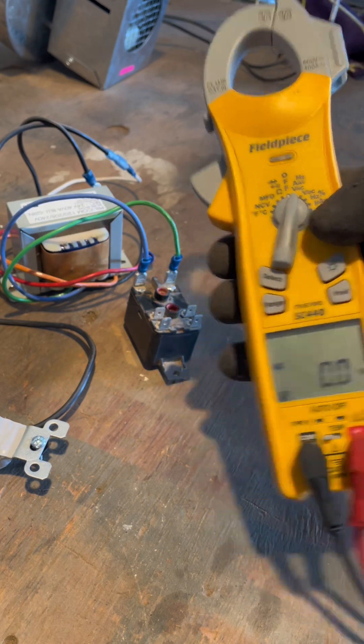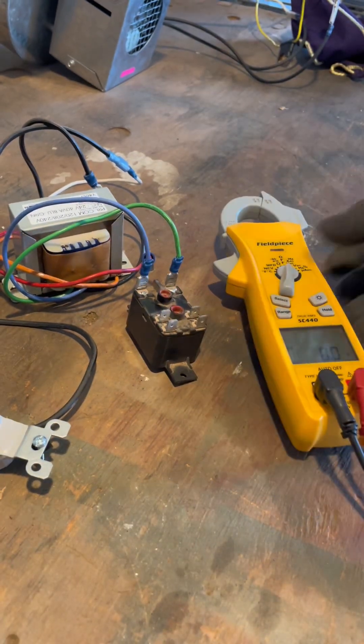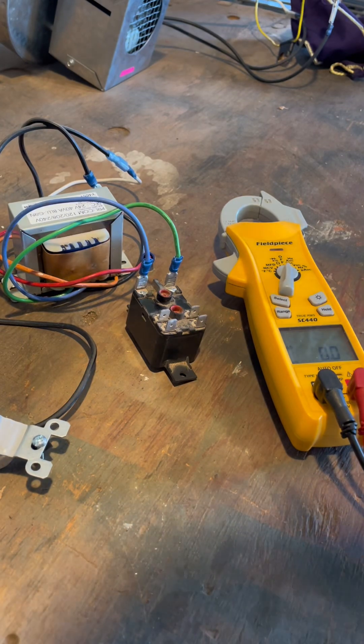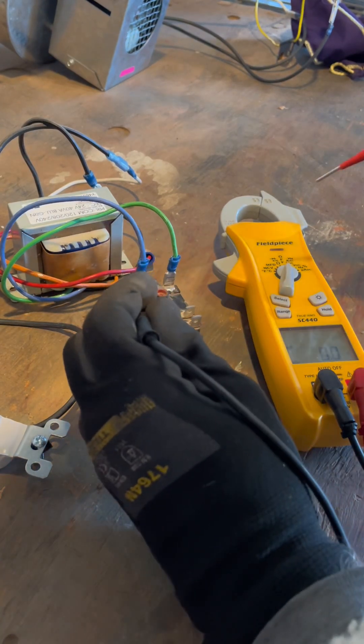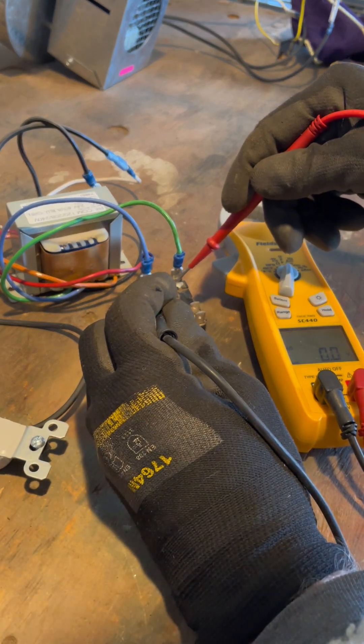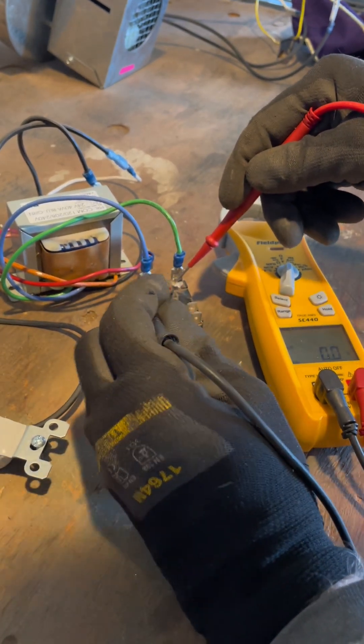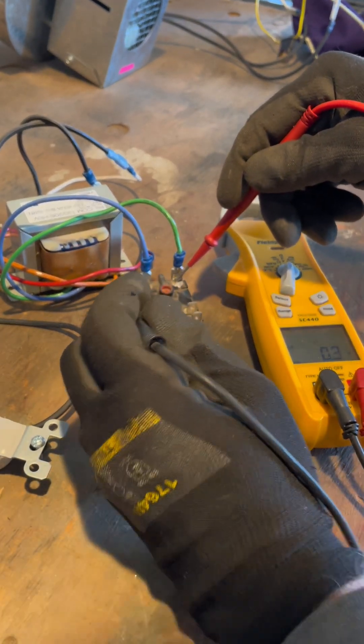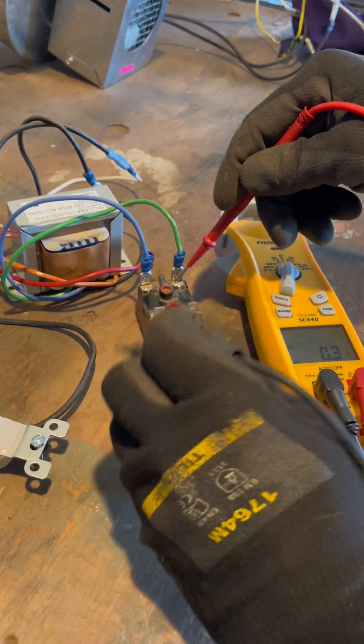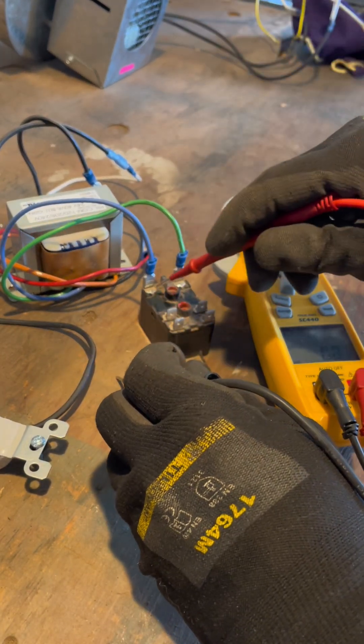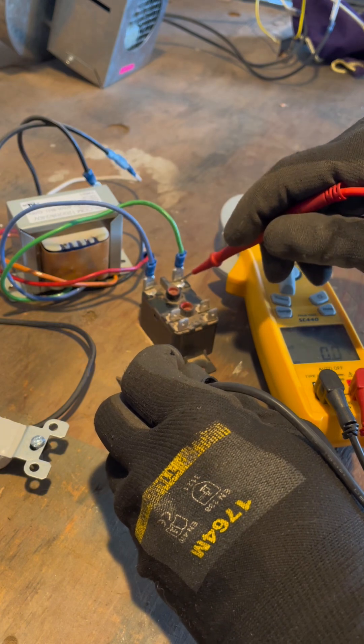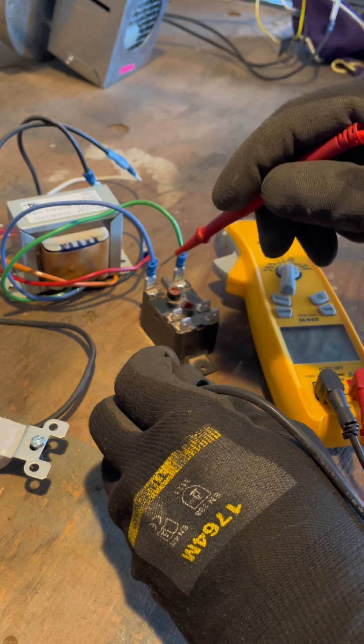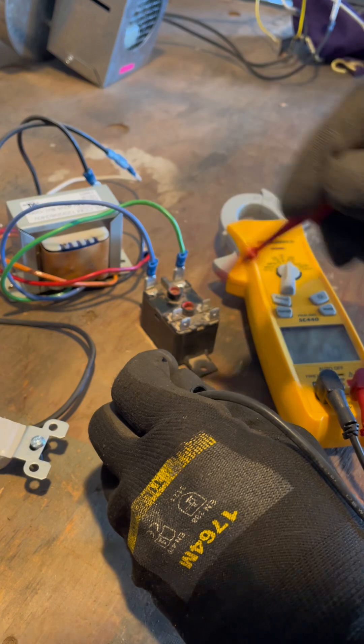Going to volts AC. I'm going to set this down right here and I'm going to test right across the coil and I am at zero. And there's another way I could do my hopscotching method where I can go find a ground in the unit somewhere, put that pin on it and I can come right up here and touch each lead and see if 24 volts is even coming from my board or coming from my transformer.